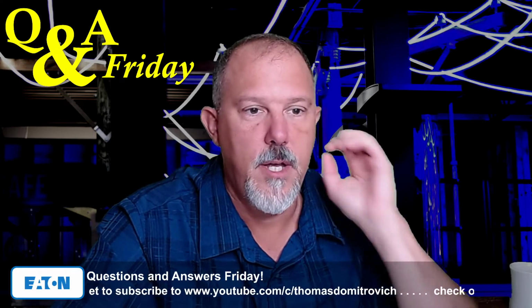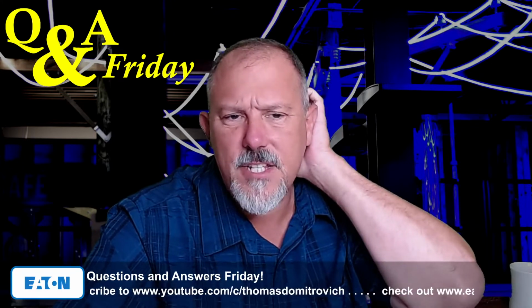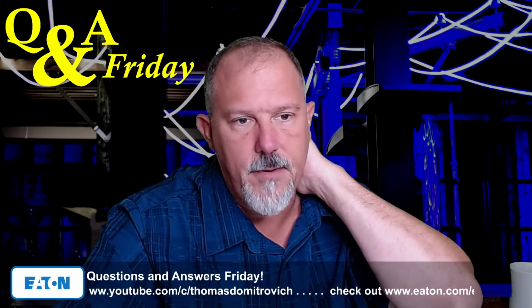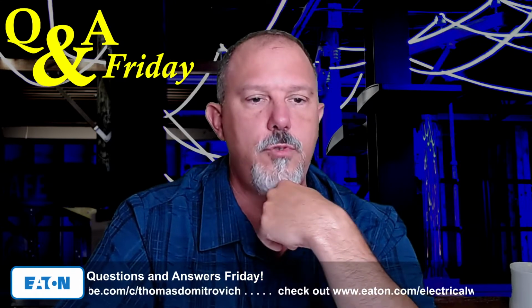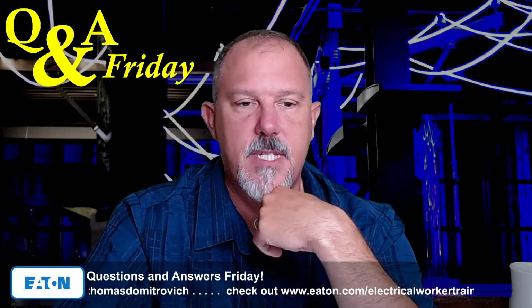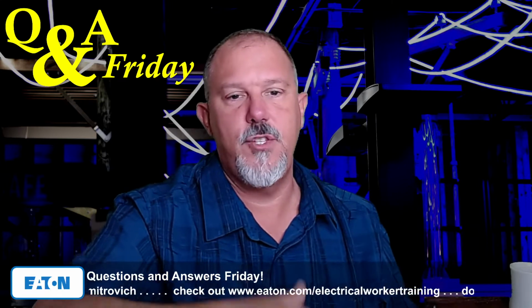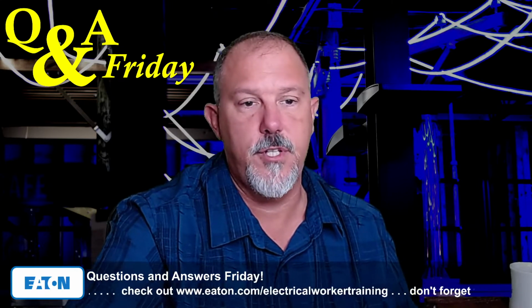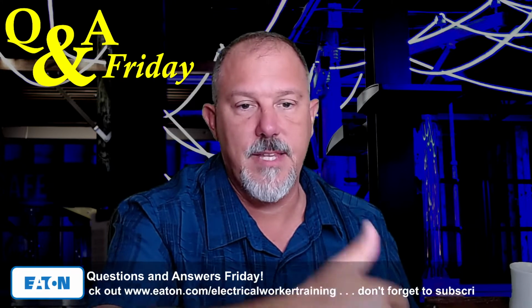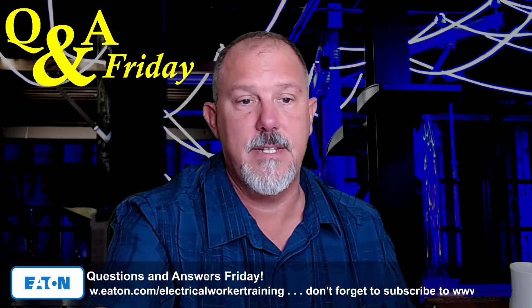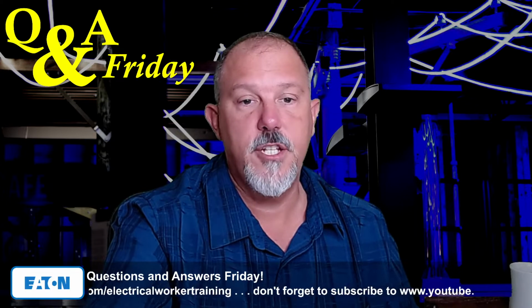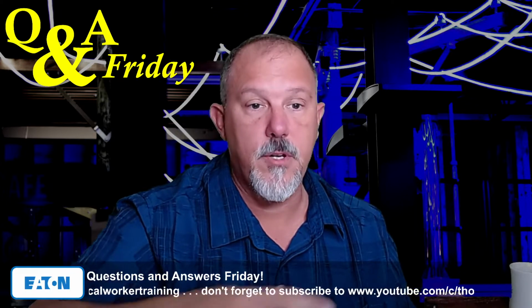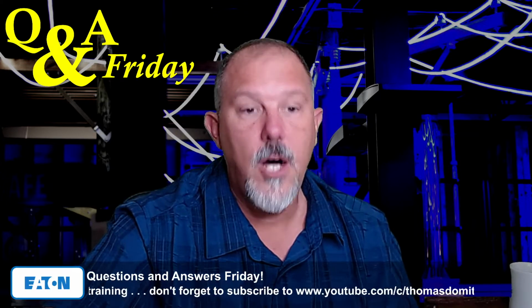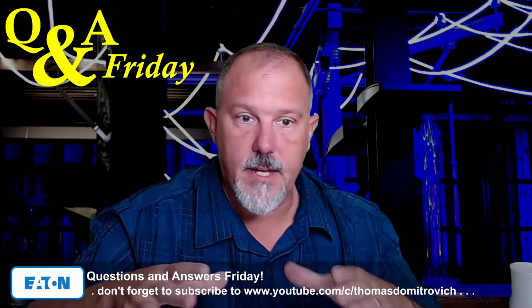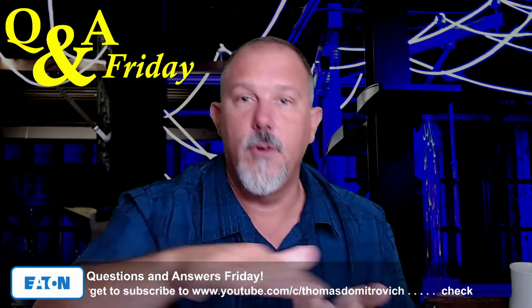Yep, JW. On my comment at minute 46 in your video, I'm speaking about things like very large customer-owned generation step-up substations, maybe 50 MVA, 250 MVA, that have secondary voltages of 35 kV and primary voltages at the higher transmission level voltages. These aren't listed assemblies or just a combination of transformer and 480 volt gear. They are separate components of things like, okay, so I think this was when you were talking about the lower voltage stuff.